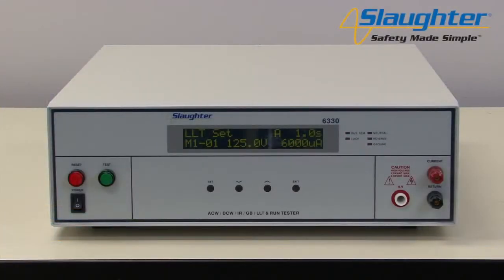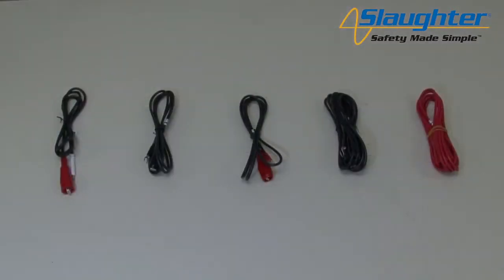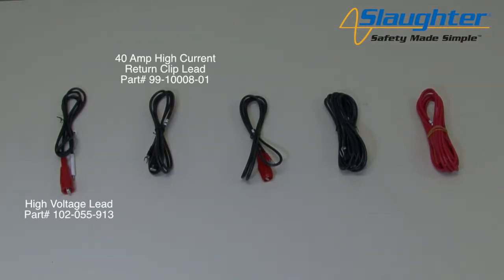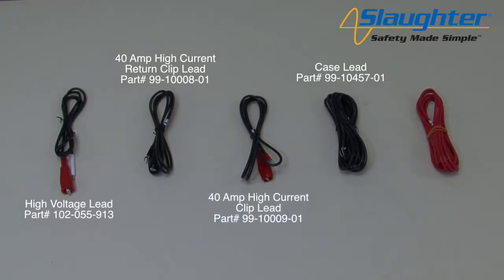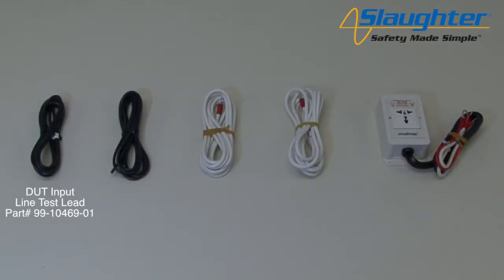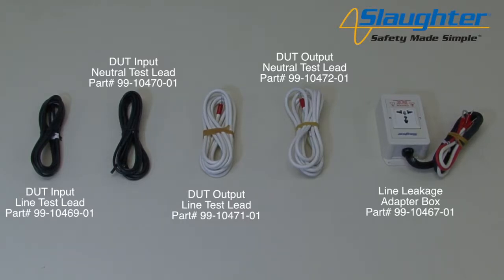Now, we're going to show you how to connect the 6330 to a DUT and run the test sequence we have set up. To connect the 6330 to the DUT, you're going to need the following accessories: the high voltage lead, the 40 amp high current return clip lead, the 40 amp high current clip lead, the case lead, the ground lead, black DUT input line test lead, black DUT input neutral test lead, white DUT output line test lead, white DUT output neutral test lead, line leakage adapter box.